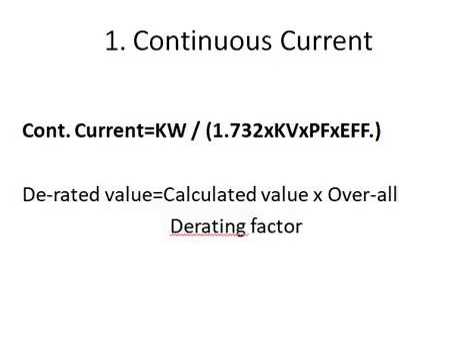Continuous current rating is calculated as: motor kilowatt rating divided by root 3, into voltage level — whether it is 400V, 480V, 6.6kV, or 11kV — into power factor, into motor efficiency. After calculating the continuous current rating, we need to apply derating factors. This derating factor includes temperature correction factor, depth of cable laying, and cable laying configuration — whether it is single-core cable, multi-layer, or single-layer configuration. The overall derating factor is calculated by multiplying all these factors.